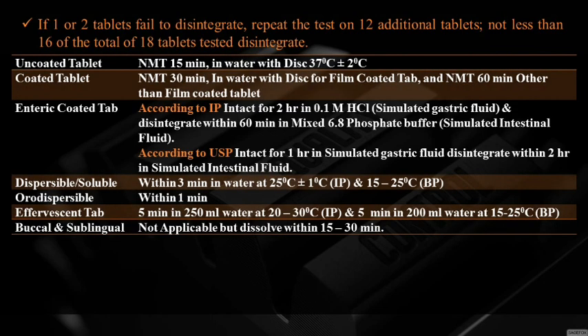If one or two tablets fail to disintegrate, repeat the test on 12 additional tablets. First, six tablets are taken in the disintegration assembly; if one or two fail to disintegrate, the test is repeated on 12 tablets, making 18 total, of which not less than 16 must disintegrate.